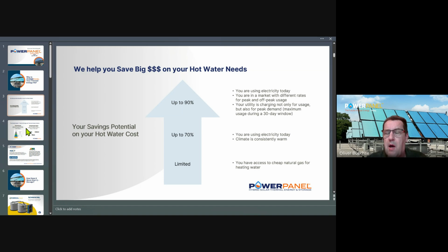That's where the heat pump comes in. The heat pump operates on electricity, but it takes one input of electricity and draws in energy from the environment, from the surrounding air and its warmth, and converts that into thermal energy. There's a ratio called coefficient of performance, or COP. So if the heat pump can create 4 units of output to 1 unit of input, that's a COP of 4. Heat pumps typically get up to 3.5, maybe under ideal circumstances up to 4. The Caribbean is an example of that, so that's the second best use case.